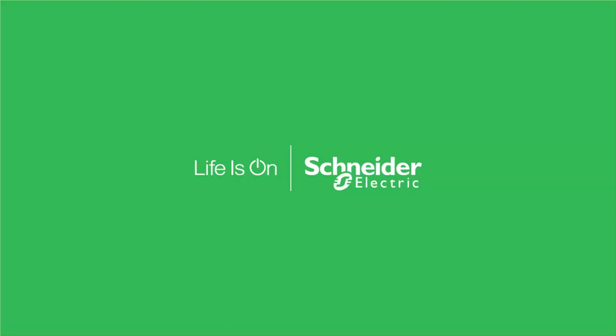Great. And what is the recommended amount of data that should be collected by the system? How many months are needed? How frequently should they log the data? And finally, where is it stored? Yeah, and that's similar to the other question. So again, 15 minutes is the typical interval for your energy management logging, and that would be absolutely for your kW demand. You would want to log that frequently. Your energy, it would be good, but typically amps, volts, power factor, those are generally logged every 15 minutes, and ideally they're logged on board the meter, and then the meter collects that and sends it back to the monitoring system host.